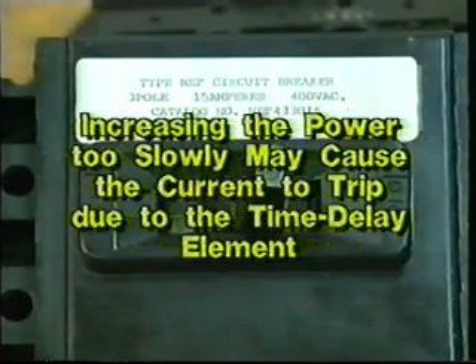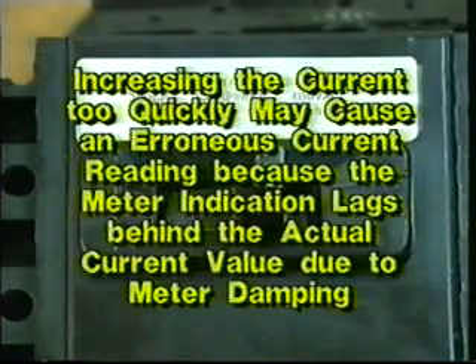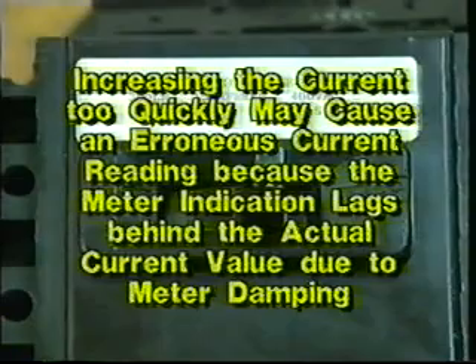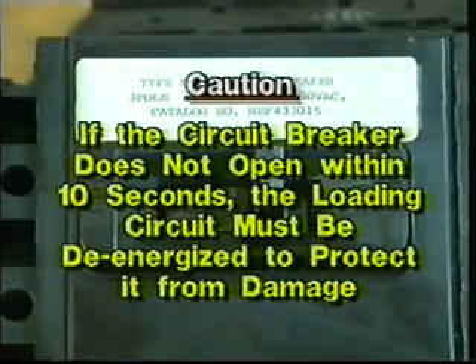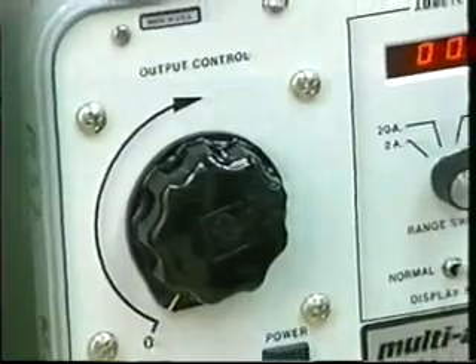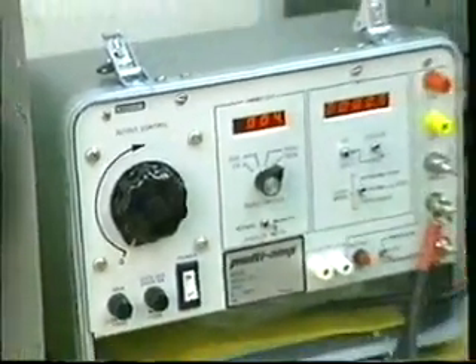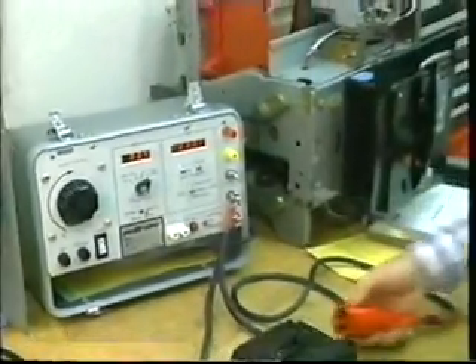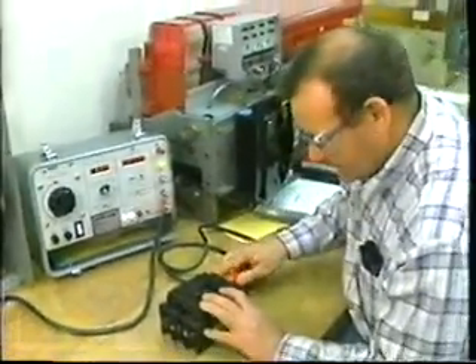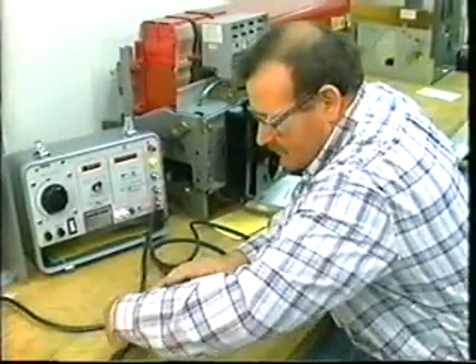Increasing the power too slowly may cause the current to trip due to the time delay element. Increasing the current too quickly may cause an erroneous current reading because the meter indication lags behind the actual current value due to meter damping. Caution: if the circuit breaker does not open within 10 seconds, the loading circuit must be de-energized to protect it from damage. The pulse method, if done properly, is more accurate than the run-up method, but it does require that the test equipment be equipped with a memory or pointer stop amp meter.